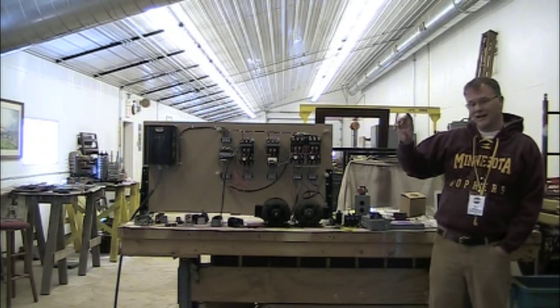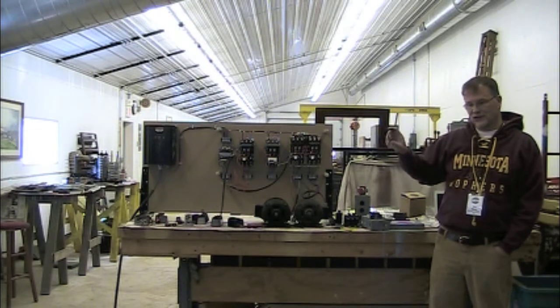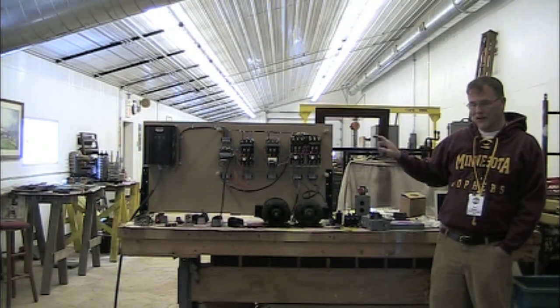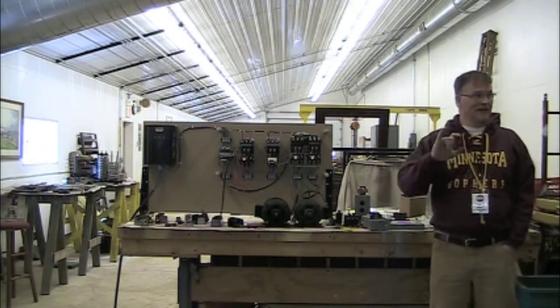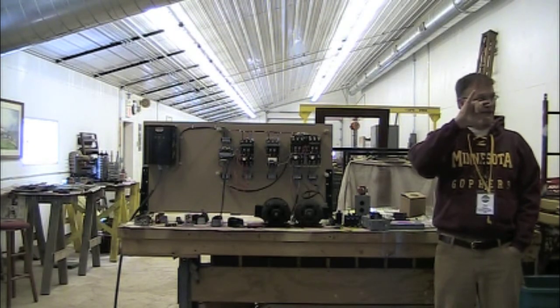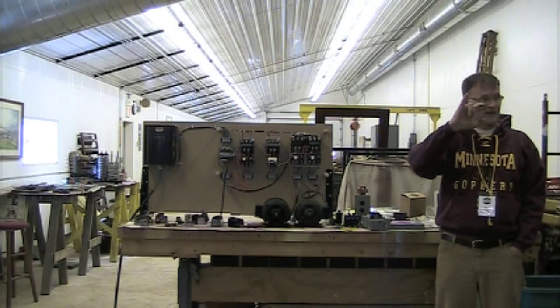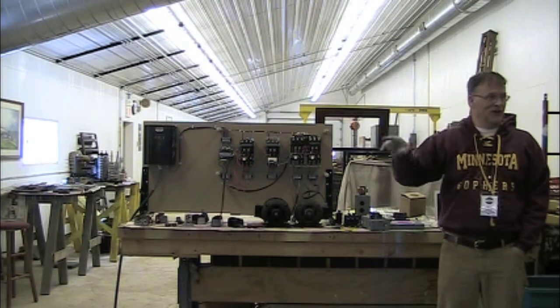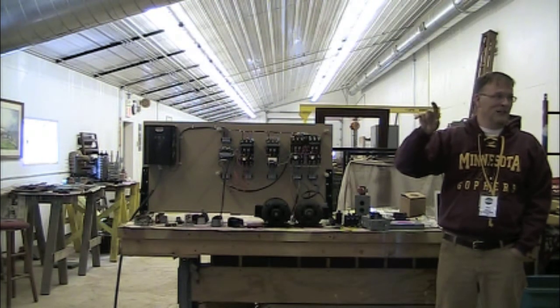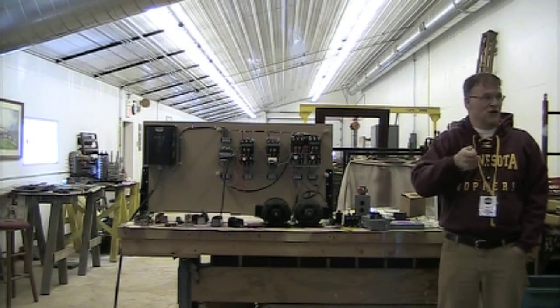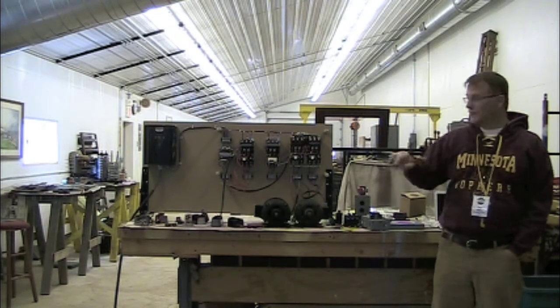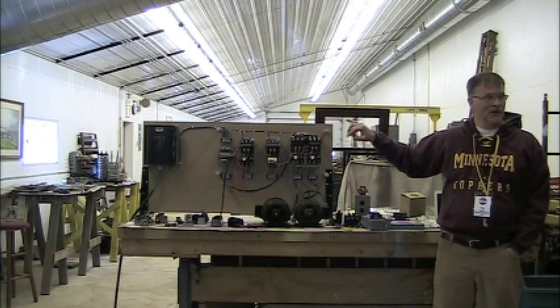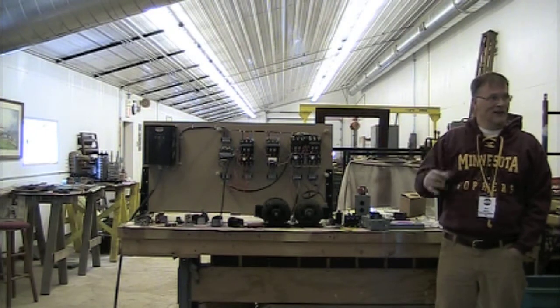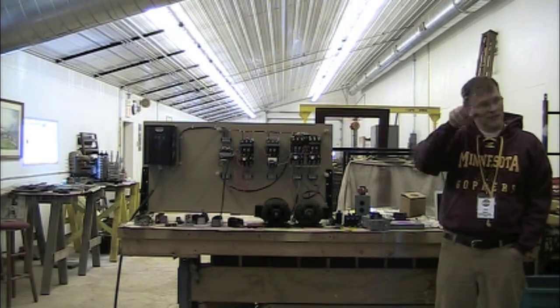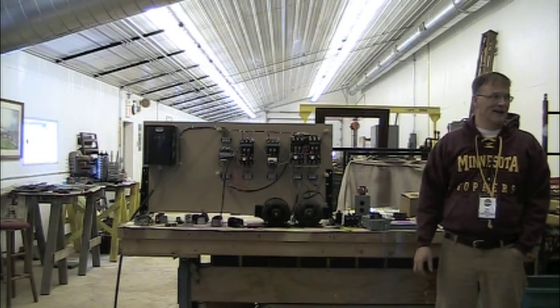Also on that side, that's one sort of isolation the control transformer gives you, because depending on how you look at that circuit, if you ground the wrong point in there, it can actually actuate the motor. You can short circuit the control circuit and complete the path to the motor just by shorting out one of the wires. So in this scenario you're not going to do that, but when you're running off line voltage and it's tied to ground, you can actually create a path by having the contact somewhere in the thing and actually close the motor circuit.